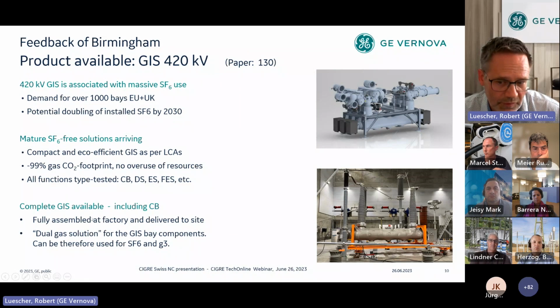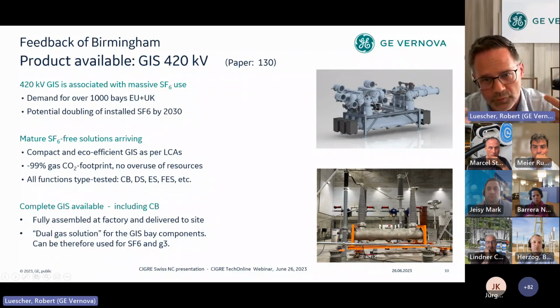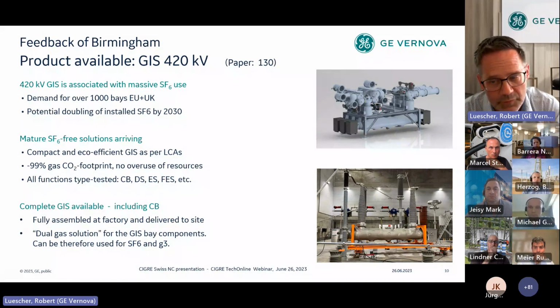Most interesting, these kinds of products are so compact, even when moving away from SF6 technology, that they can be fully assembled at the factory and delivered to site. So that saves a lot of trouble for the installation. We call it dual gas. The system is designed to be used with SF6, and it can also be used with our new technology based on fluoronitrile, which gives the opportunity to even start with SF6 and later convert to a fluoronitrile-based solution, or to start from scratch directly, completely SF6 free.